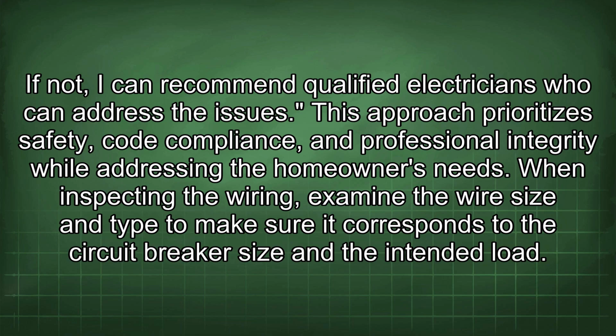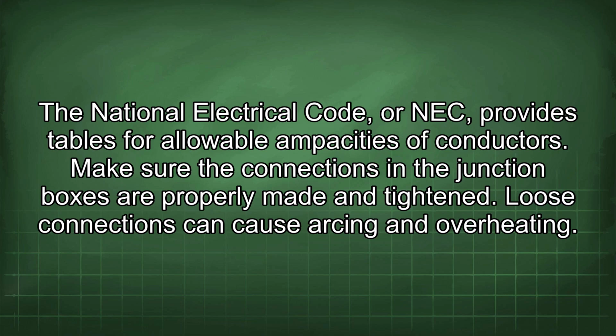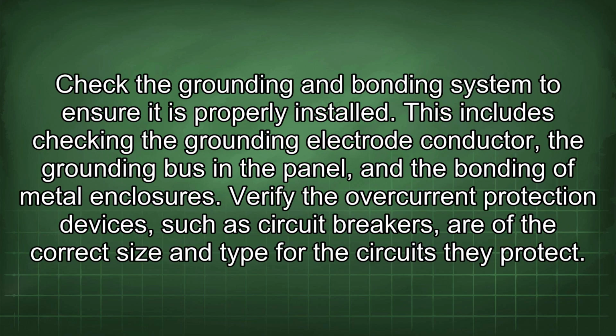When inspecting the wiring, examine the wire size and type to make sure it corresponds to the circuit breaker size and the intended load. The National Electrical Code, or NEC, provides tables for allowable ampacities of conductors. Make sure the connections in the junction boxes are properly made and tightened. Loose connections can cause arcing and overheating. Check the grounding and bonding system to ensure it is properly installed. This includes checking the grounding electrode conductor, the grounding bus in the panel, and the bonding of metal enclosures.